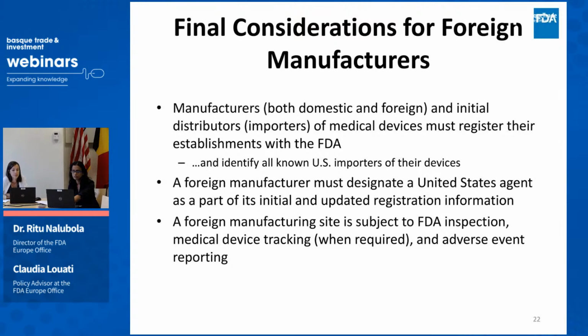Final considerations, of course: manufacturers, both domestic and foreign, as well as initial distributors of medical devices, must register their establishments with the FDA, as well as identify all known US importers of their devices. So that's something very important. Sometimes we get the question of, I'm a foreign manufacturer, do I need to register? Yes, you do. And there are also specific listing requirements in terms of the devices that you put on the market. As Richard mentioned, foreign manufacturers must designate a US agent in order to facilitate communication with the agency. And of course, the manufacturing site is subject to FDA inspection, medical device tracking when required, and adverse event reporting.